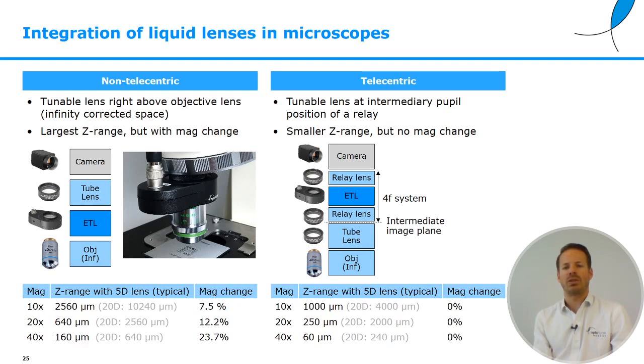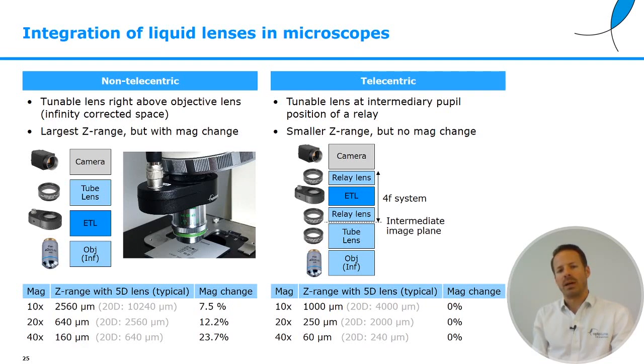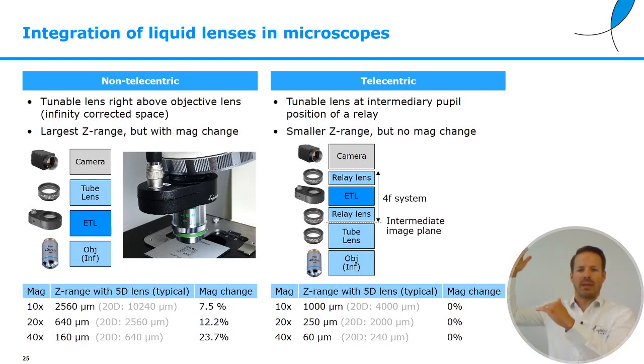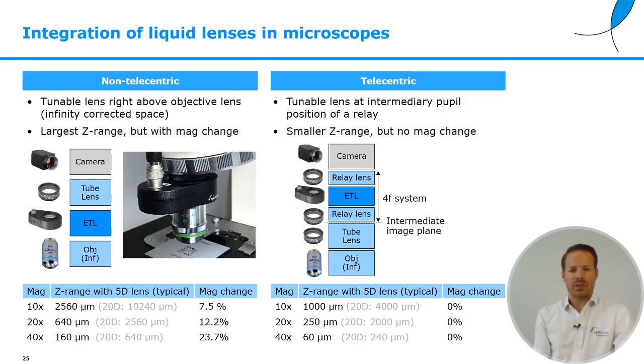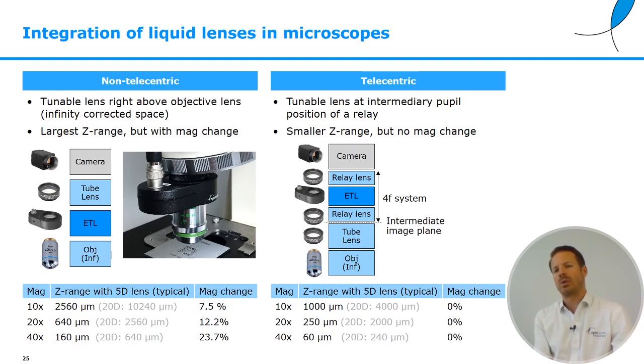To avoid the magnification change, you can place the liquid lens into an intermediary pupil position, formed by adding relay lenses behind the image plane — a 4F system. You can add the relay on top of an existing camera port and get no magnification change. However, the Z range is typically a bit lower — for example, 60 micrometers on a 40x magnification. There is the option to use more than a 5-diopter lens; we provide lenses up to 20 diopters, where the Z range could be extended again.